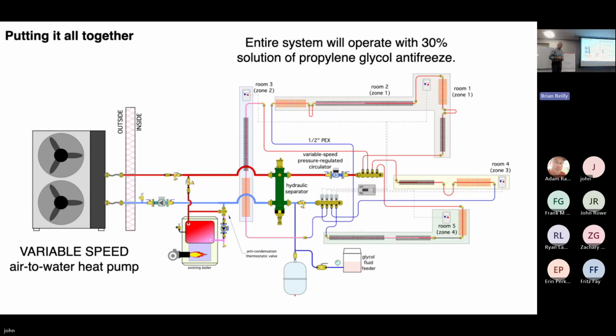Another approach would be to use really low mass heat emitters like panel rads, or fan coils, and then you could switch. If you did it all with fan coils, so you have very low mass, they could instantly switch between heating and cooling. Back in the mechanical room, how do I want to set that up? If there's a possibility of simultaneous heating and cooling, I'm probably looking at 2 buffer tanks to do that.